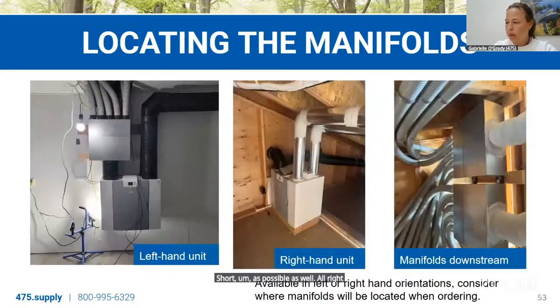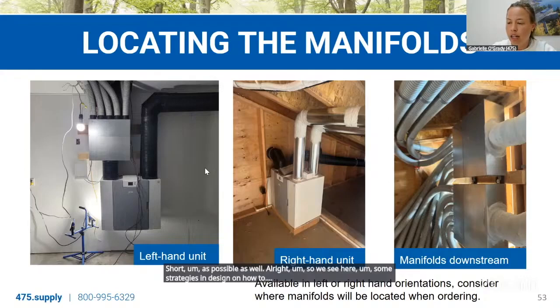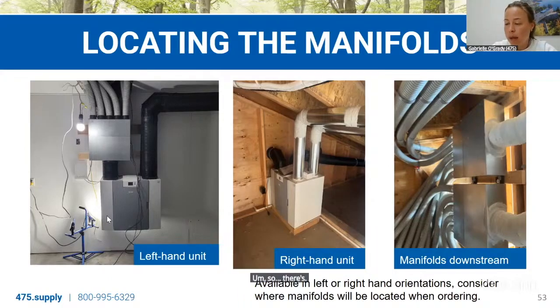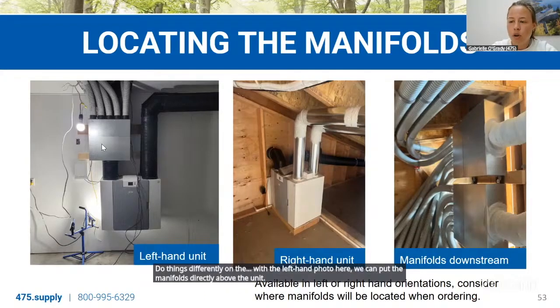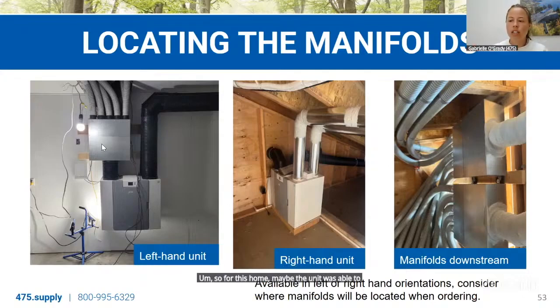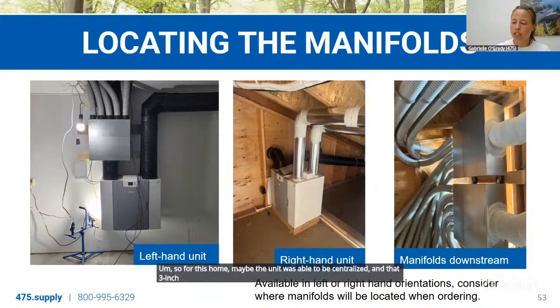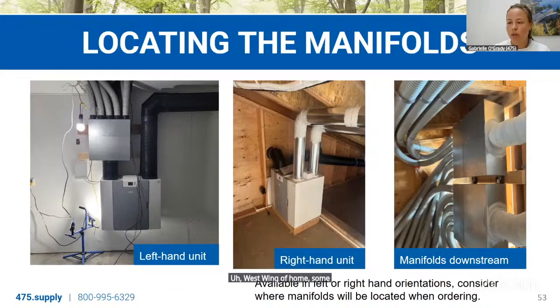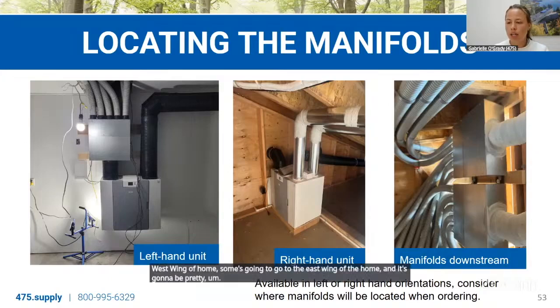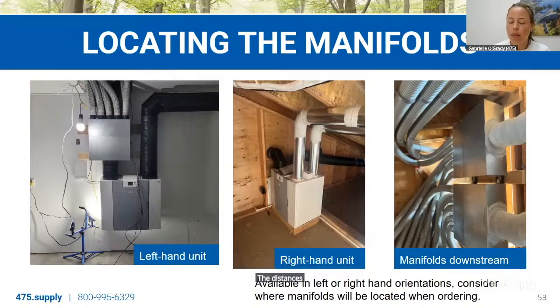All right. So we see here some strategies in design on how to increase the efficiency of the full design system. Depending on the home, you might do things differently. With the left-hand photo here, we can put the manifolds directly above the unit. So for this home, maybe the unit was able to be centralized, and that 3-inch ductwork is some of it going to go to the west wing of the home, some's going to go to the east wing of the home, and it's going to be pretty equal. The distances of that ductwork are going to be pretty equal.